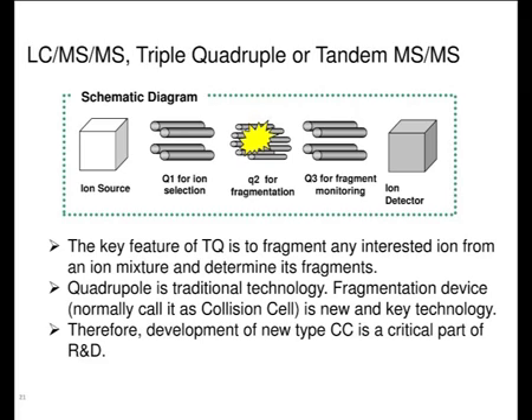This is not the only technique possible. There are different modes, like MRM, multiple reaction monitoring, the precursor ion scan, and the neutral loss scan. Different modes have different applications, which we are going to discuss in a subsequent slide. In short, the difference between single and triple quadrupole is that with triple quadrupole you can fragment your compound of interest, generate more information, and by selecting particular fragment ions, you can do quantification of your compound of interest.